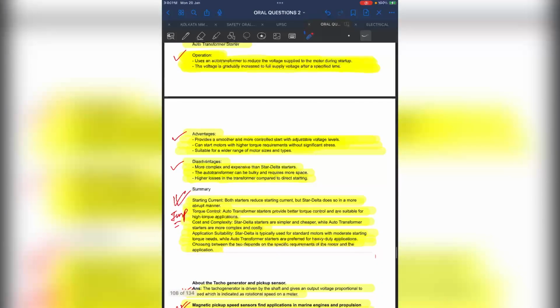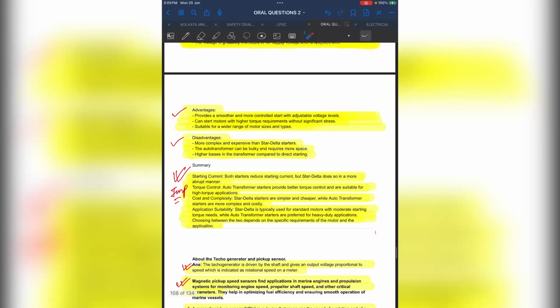But the auto transformer starter uses an auto transformer to reduce the voltage supplied to the motor during startup. Here also we reduce the voltage, because there is a tapping, and based upon the tapping we provide the voltage. We provide the reduced voltage at the time of starting, and when the motor reaches approximately synchronous speed or full speed, then we can provide the full voltage. The voltage is gradually increased to the full supply voltage over a specified time.